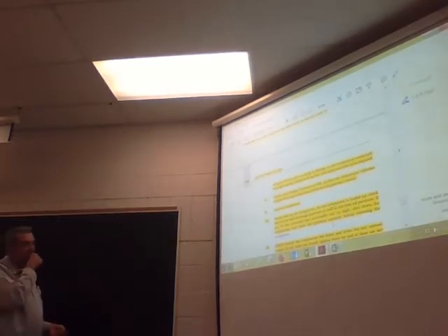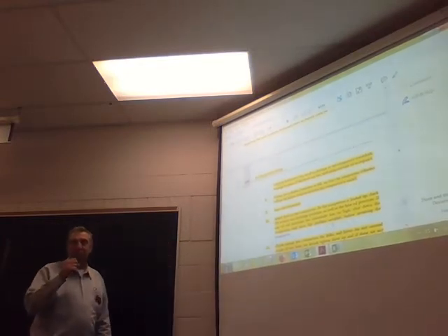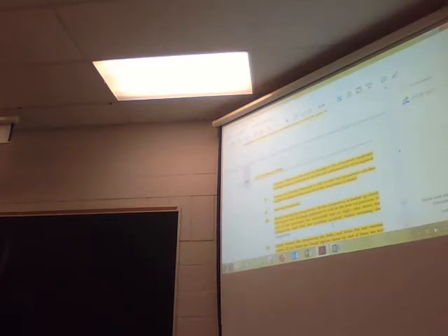Start the compressor. Slowly load up the compressor. Keyword being slowly. Just like starting with water. Bring her up slow. As the compressor is loaded up, check the suction and discharge pressures as well as the lube oil pressure.